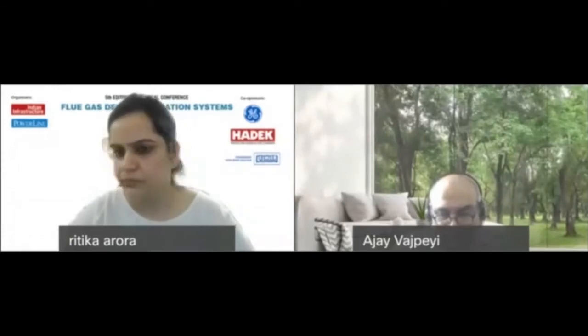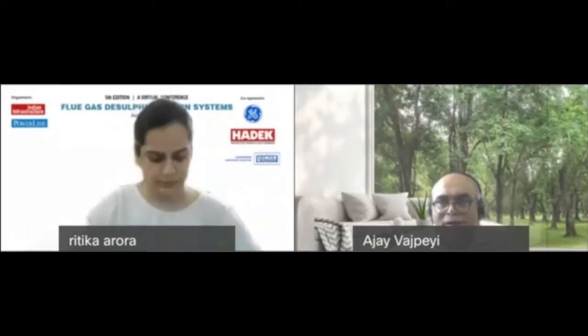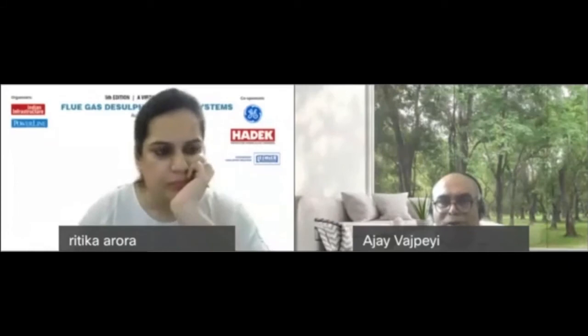Is the gypsum quality dependent upon wash water quality? The wash water quality is basically needed to control the amount of chloride you get in the gypsum, so it will determine the chloride content after the wash. Other than that, gypsum quality is governed by the quality of water in the plant, the limestone quality needed, and whether there's any dust coming in from the ESP to the absorber.